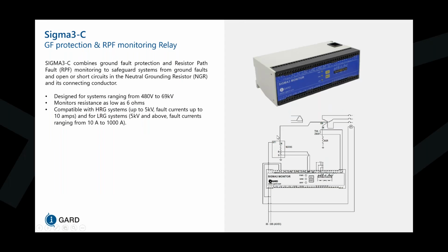In addition to that, the sensing resistor also gives us a reference for neutral voltage, and our CT is also giving us a reference for neutral current so that we can also pick up ground fault conditions. Now it's designed for systems ranging from 480 volts to 69 kV. We can monitor resistances as low as 6 ohms, and we're compatible with HRG systems up to 5 kV, as well as LRG systems beyond 5 kV with currents ranging from 1 amp all the way to 1,000 amps in both configurations.